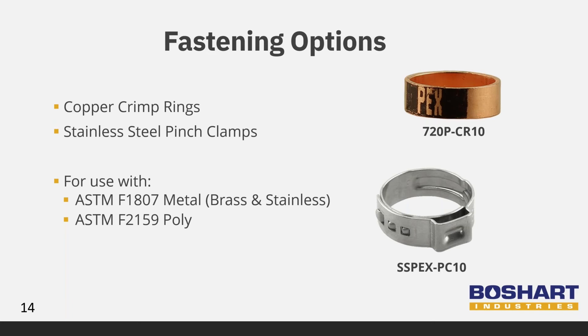PEX pipe is fastened to these PEX fittings and valves by using one of two options. Boshart Industries offers both copper crimp rings and stainless steel pinch clamps for fastening the pipe to the fittings. Each system uses a special tool to create a watertight seal. Both of these fastening options work with ASTM F1807 metal fittings, such as stainless and brass, as well as ASTM F2159 poly fittings.